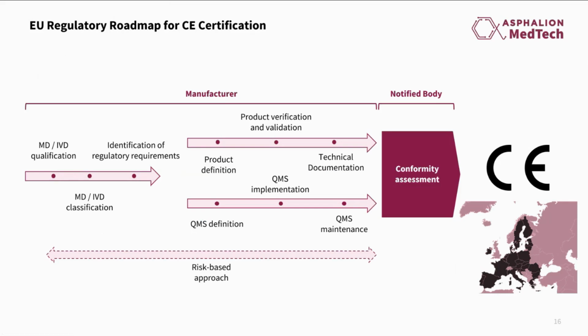All in all, the whole roadmap for reaching the CE mark in Europe is represented, as you can see, in the slide. Basically, the first part is the strategic part, where you first need to assess what we have done so far: the qualification as a medical device or an IVD. This means reviewing whether the definition of medical device or IVD is applicable to you. Then, if so, conduct the classification analysis to see whether your device is class 1, class 2A, class 2B, or class 3. And then, following this classification, identify primarily what the regulatory requirements will be.